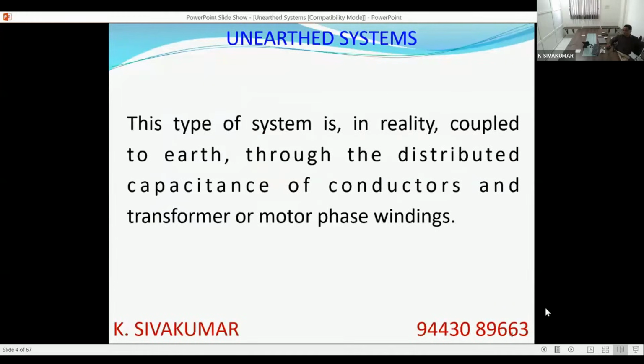But even when we say it is an unearthed network, whether you like it or not, there will be capacitive coupling prevailing between each conductor and the earth. Because, as you know, two conductors separated by a dielectric form a capacitance. In this network also there will be conductors and there will be a dielectric. If you take an overhead distribution line, the overhead line will be one plate of a capacitor, natural ground will be the other plate, and the air in between will act as the dielectric, so a capacitance is formed. So there will be an imaginary capacitive coupling, even though we cannot call it a wired coupling. There will be a capacitive coupling throughout the system. It will persist. Even though we say physically unearthed, it will be a capacitively earthed system.